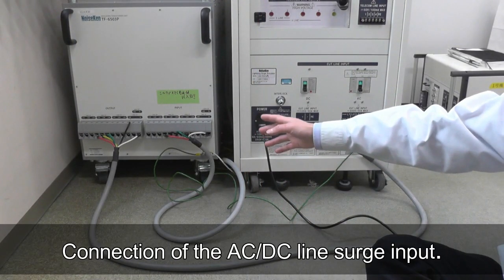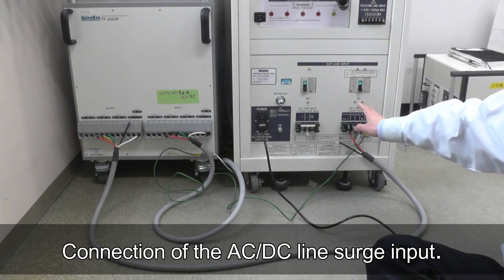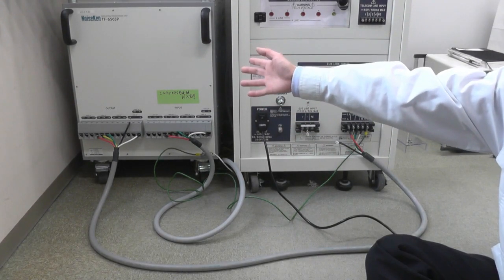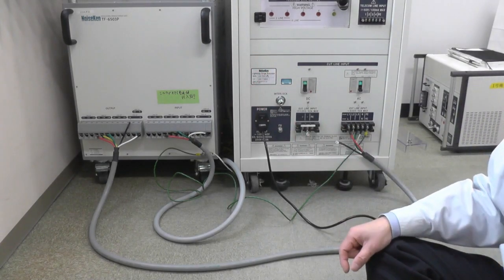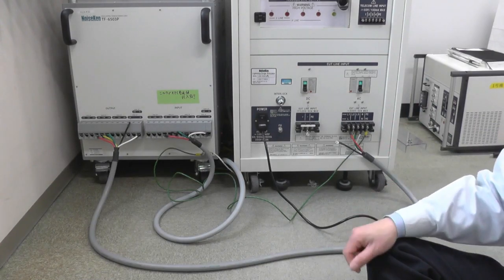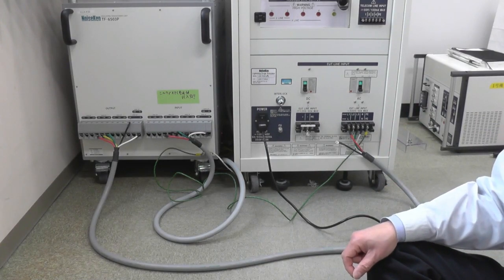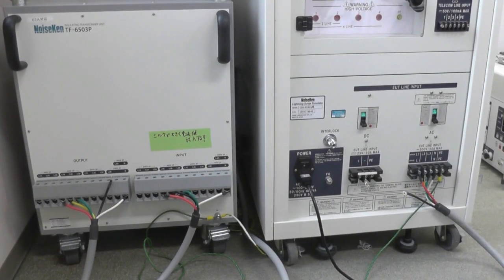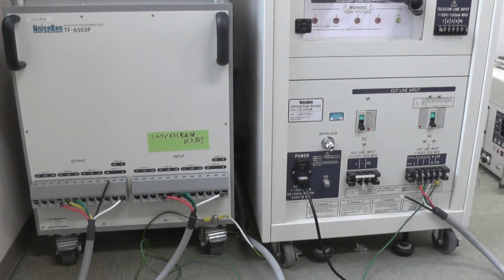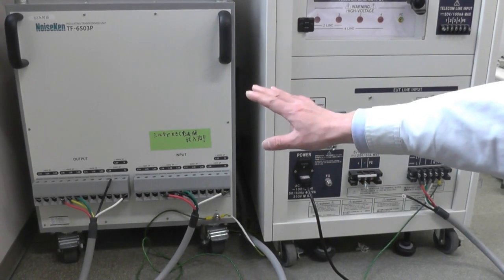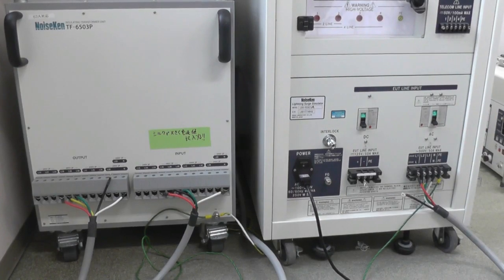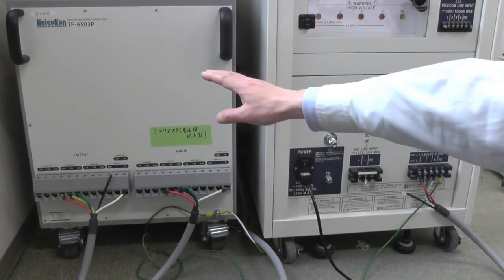When applying a surge waveform on an AC line, be sure to use an isolation transformer to supply AC power to the AC line input terminal of the lightning surge simulator. If AC power is applied directly without an isolation transformer, the leakage circuit breaker of the building's main power may be activated by the back surge. Before connecting the isolation transformer, make sure both the isolation transformer and the lightning surge simulator are powered off.